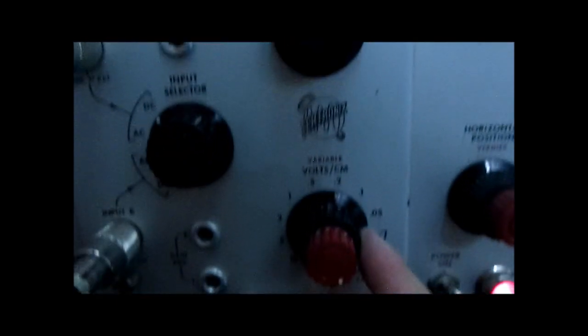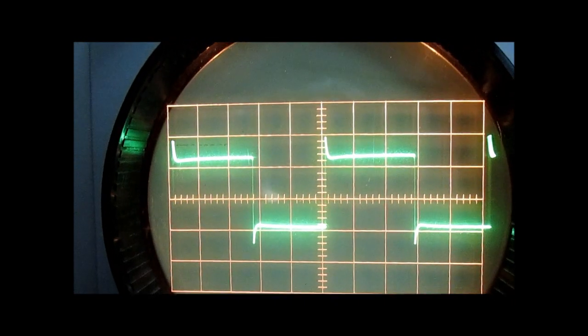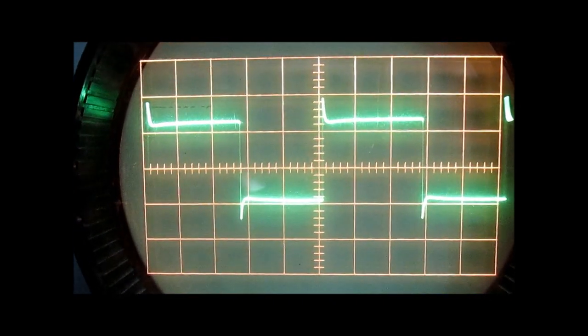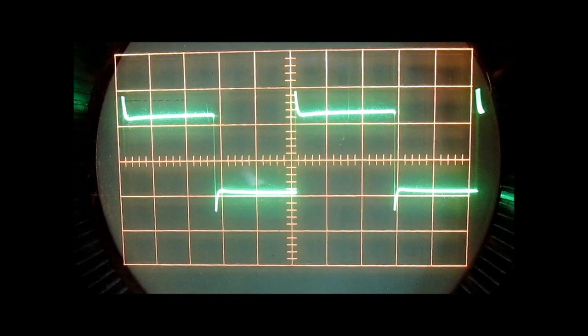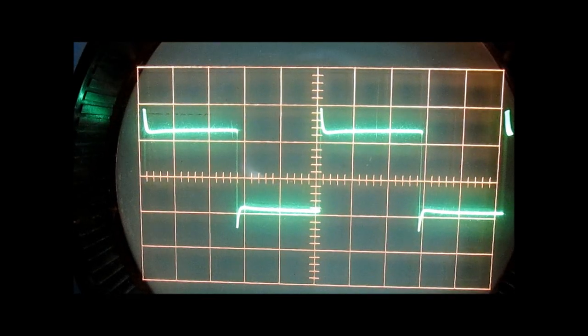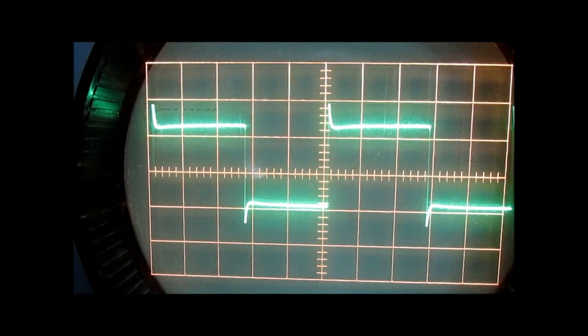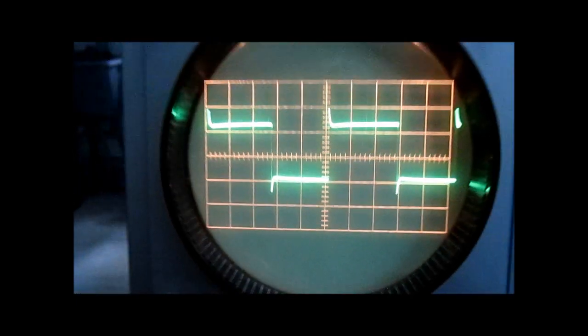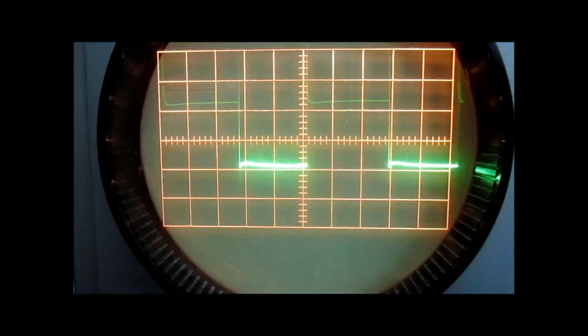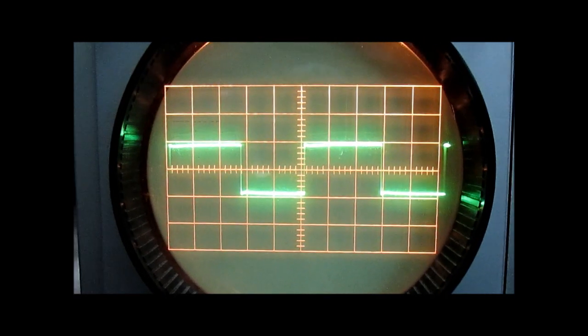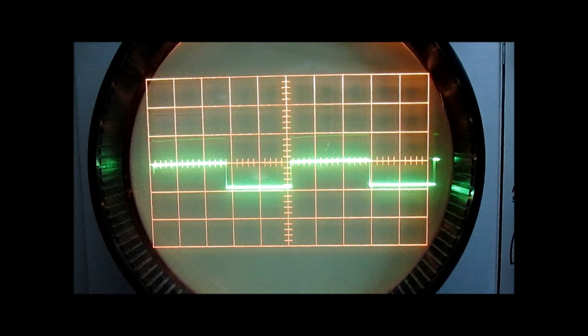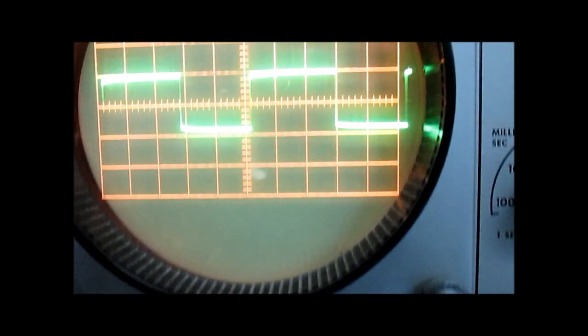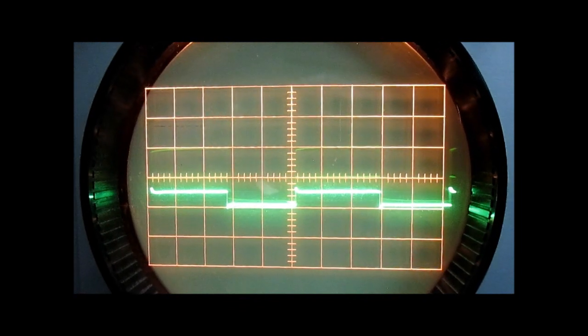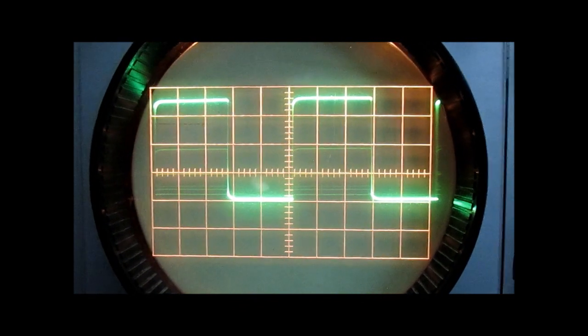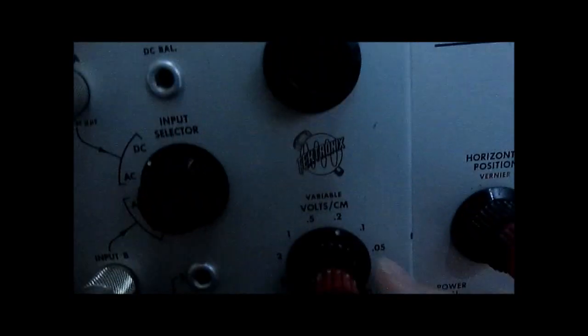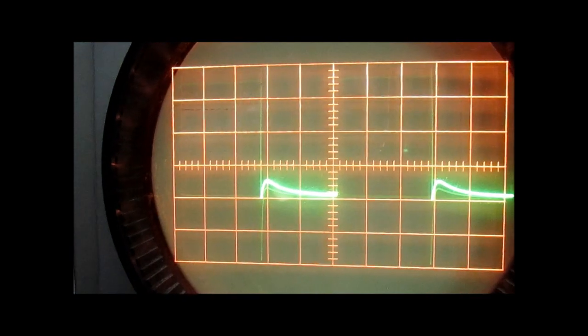But going back to 0.2, we got this horrible overshoot, undershoot. So the problem here is after the input networks, when it gets into the gain selector or the attenuator selector switch, is where the problem lies. And if we look at some of the other inputs, that one is okay. We turn that one down, turn that one on. That one has got a little bit rounded off. But these lower ones seem to have more of an issue.